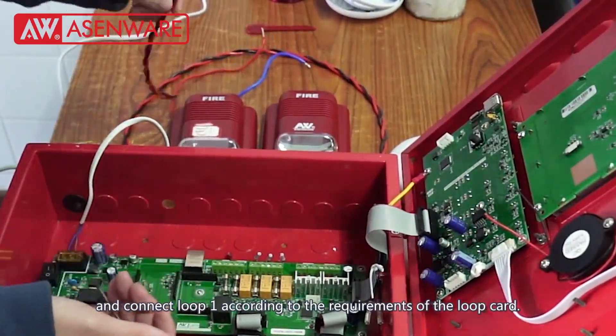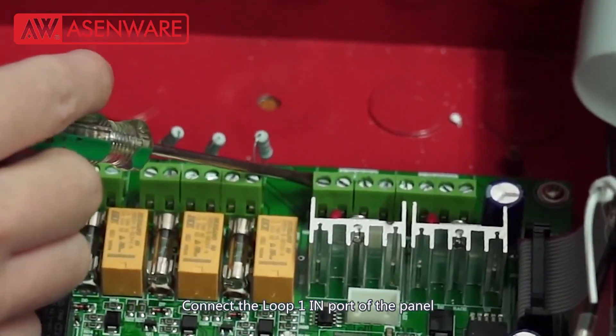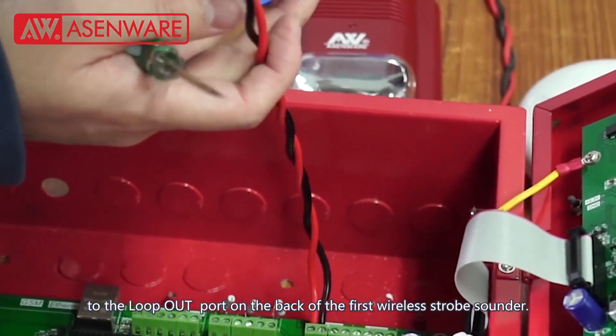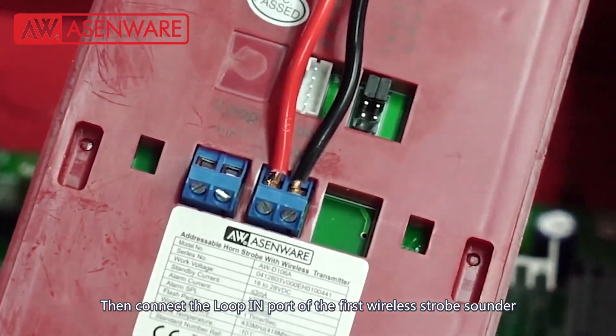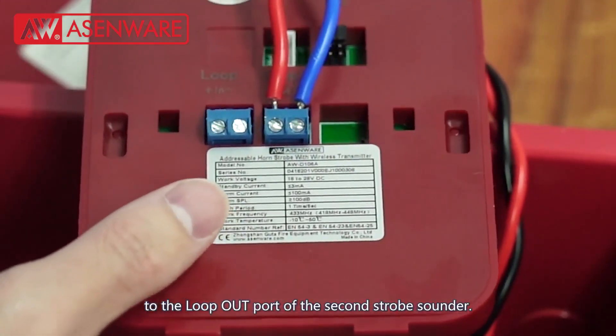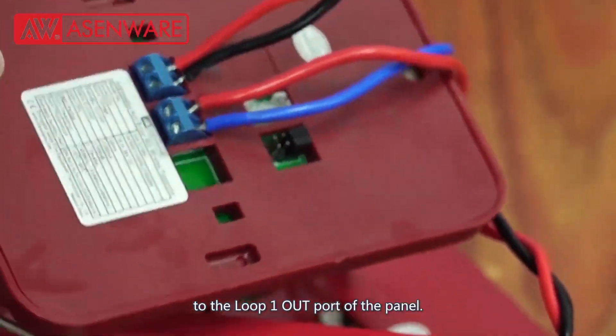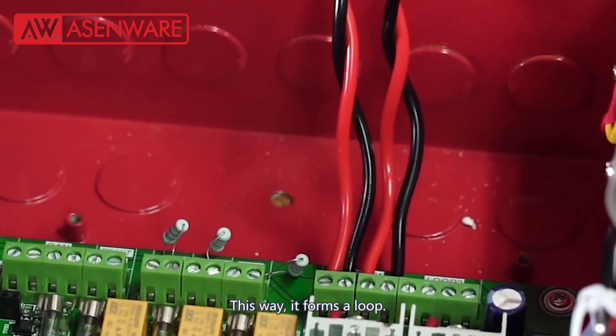Open the AWFP100 addressable fire alarm panel and connect loop 1 according to the requirement of the loop card. Connect the loop 1 in port of the panel to the loop out port on the back of the first wireless strobe sounder. Then connect the loop in port of the first wireless strobe sounder to the loop out port of the second strobe sounder. Finally, connect the loop in port of the second strobe sounder to the loop 1 out port of the panel. This way it forms a loop.